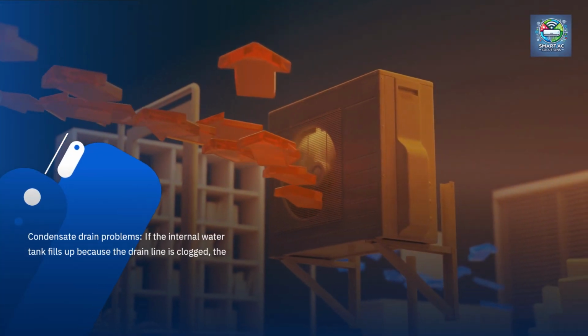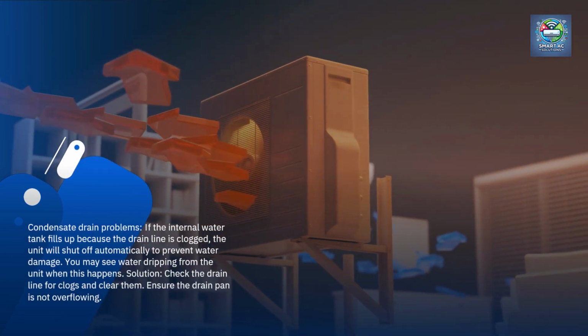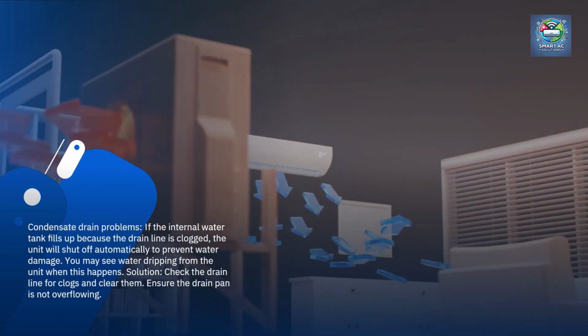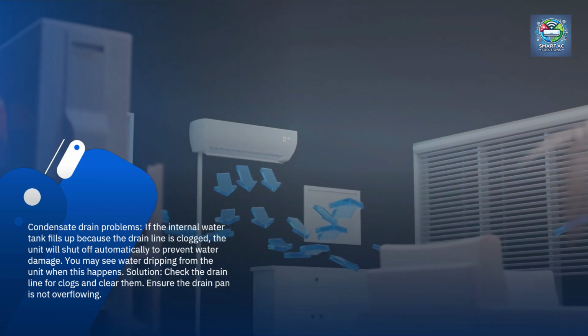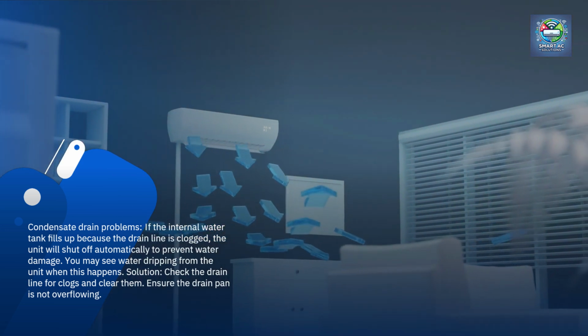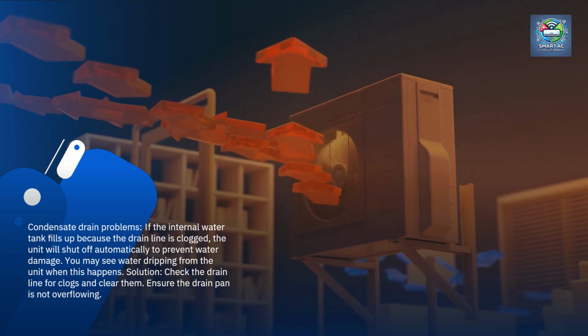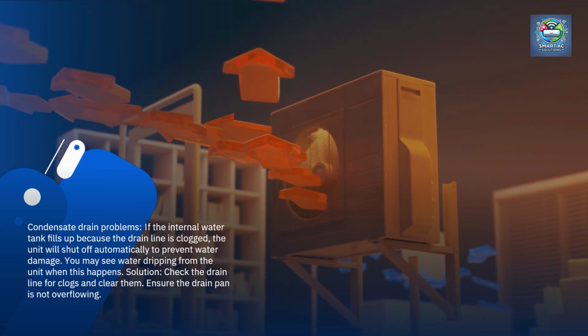Condensate drain problems. If the internal water tank fills up because the drain line is clogged, the unit will shut off automatically to prevent water damage. You may see water dripping from the unit when this happens. Solution: check the drain line for clogs and clear them. Ensure the drain pan is not overflowing.